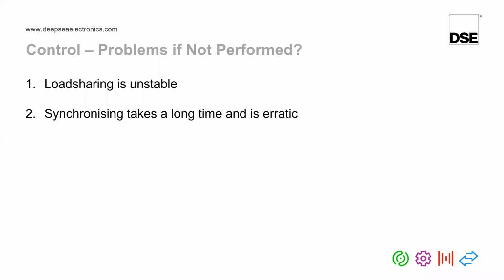I'd just like to add a few points onto that as well. What Dave said is completely correct. Yes, sometimes you won't get exactly 80%, as Dave's mentioned, because of how fine the switch 2 setting is. And that's, again, not a problem. That's why we've said you need to be in that range of 75 to 85%.